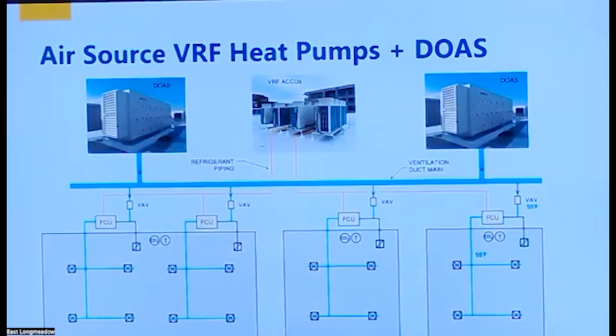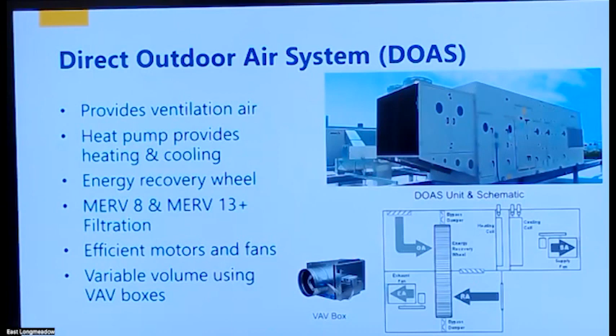So these are those dedicated outdoor air system units. In the bottom right, that's a schematic of it. It's all the moving parts in there, which I'm not going to really get into. But the important thing is that it's providing a really good level of filtration of that outdoor air. It's got that energy recovery wheel that I mentioned that transfers air energy from the exhaust air to the outdoor air to help condition it before we actually mechanically cool it or heat it. And then, as I mentioned, those VAV boxes, which are essentially a damper, which throttles the air, or it'll open to let more air in, or throttle to reduce the air based on carbon dioxide levels. Next slide, please.